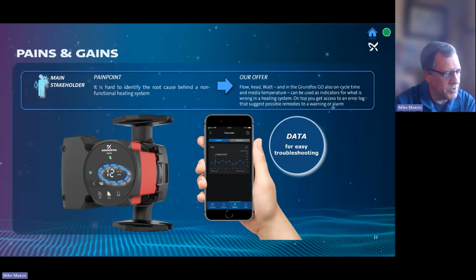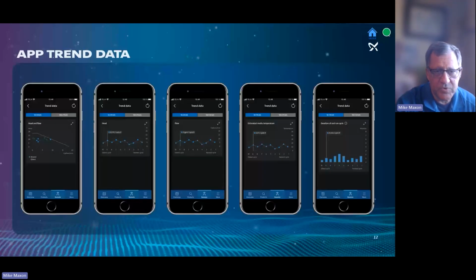So the pump does collect data as far as where it's been running. And with that and with the screen, you could do some simple troubleshooting on the spot. With the screen, you can see what the head of the system is, what the flow is, and what the wattage of the pump is, simply, like I said, by touching it. But if you connect with the phone, this is on the Alpha, you can see the trend data. And here's an example of the trend data.